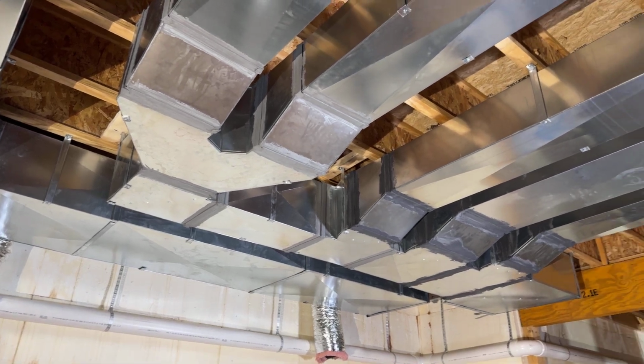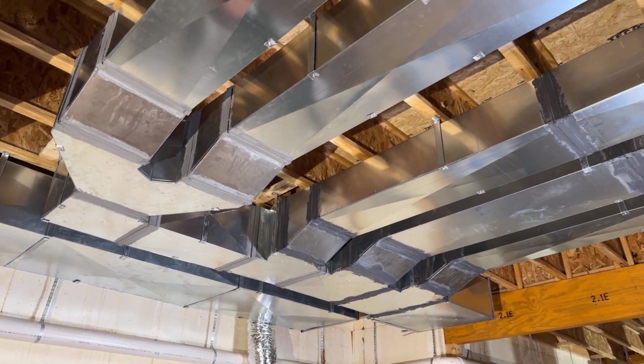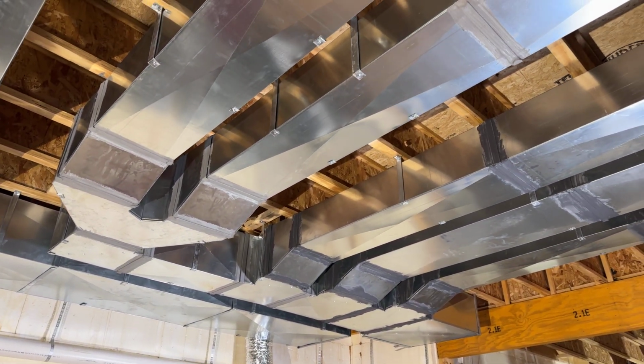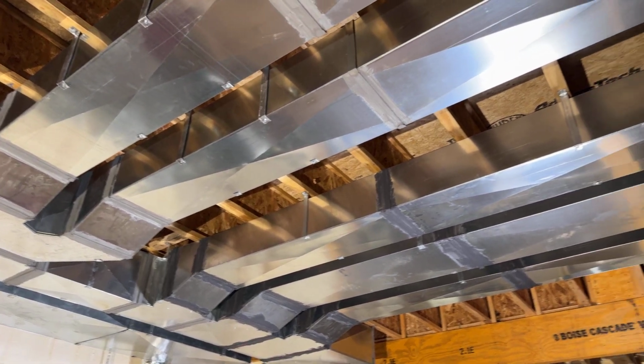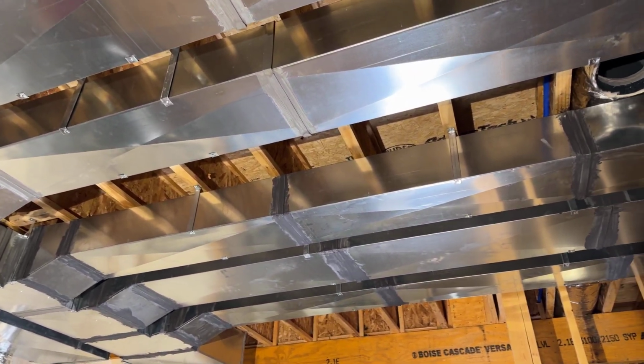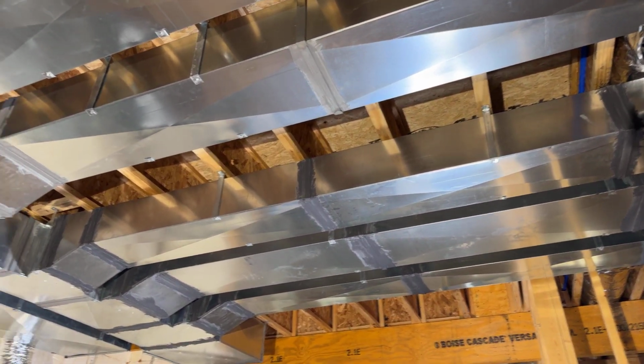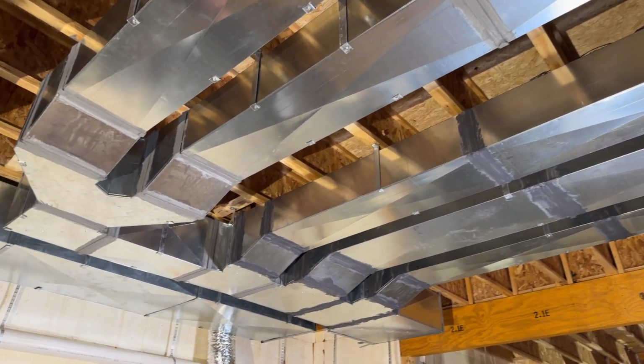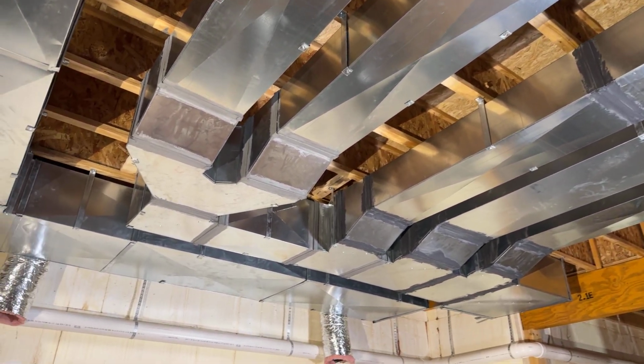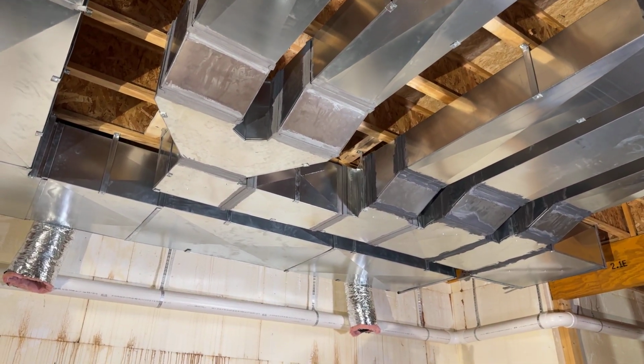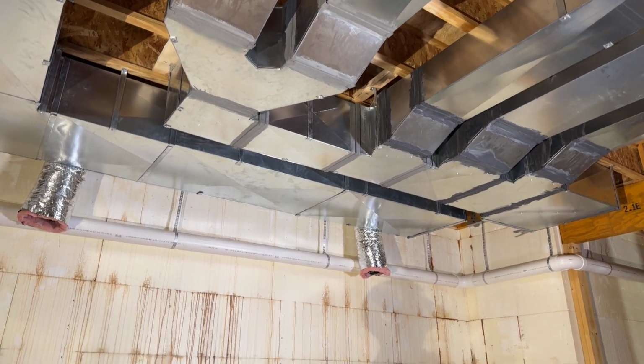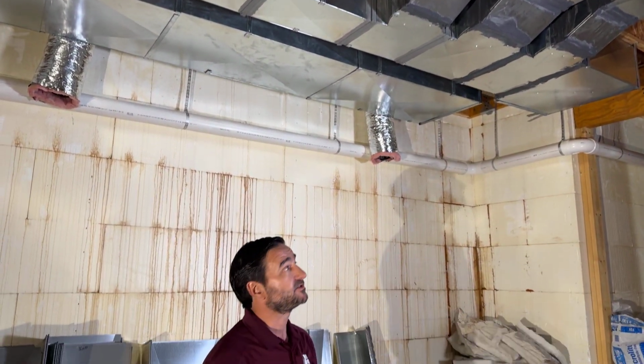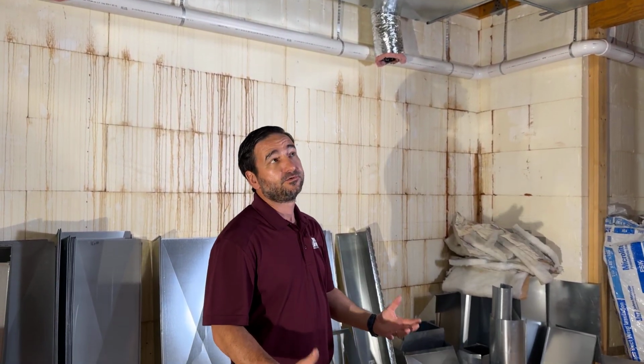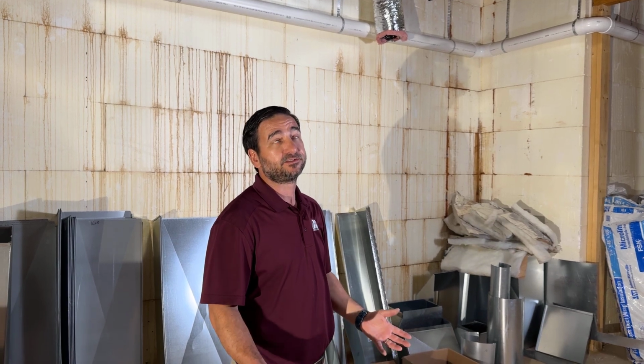In this case, it'll be a WaterFurnace geothermal unit, and we can have up to 6 different thermostats on this system. In this configuration, we're going to have 5, and you can see that each zone is represented as its trunk duct. So the trunk duct is a square duct that runs down where the branches come off to hit the different registers. When you are doing a zone system, a couple of things are very important.